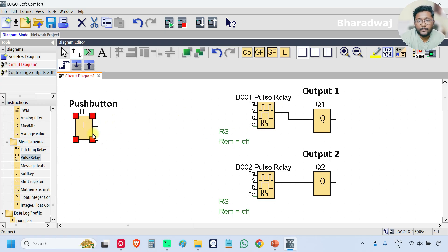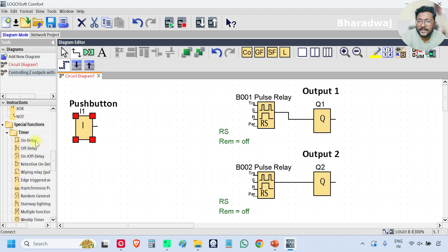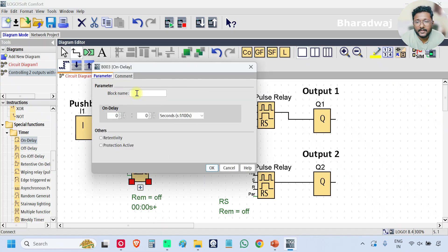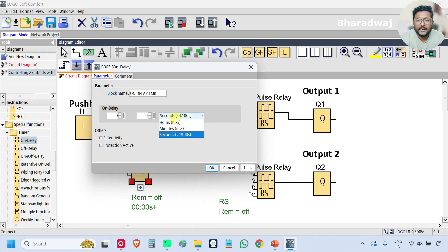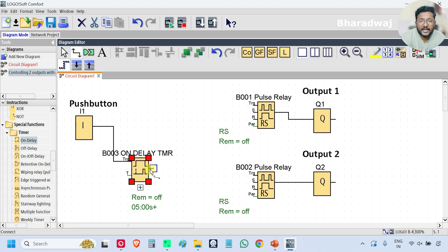For output two I need one on-delay timer, because after five seconds only output two will be controlled. That is why I have taken one on-delay timer and set it to five seconds. Connect the push button to the on-delay timer input, and connect the output of the on-delay timer to the pulse relay.